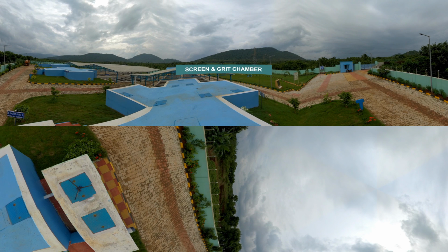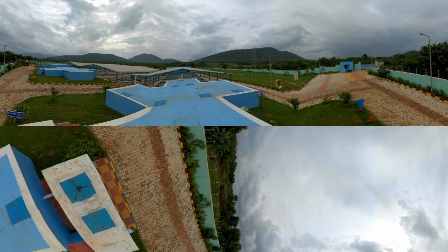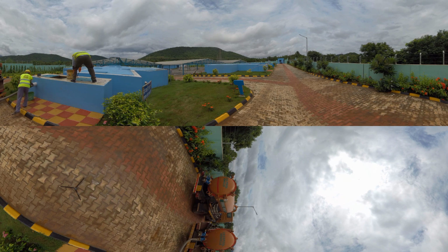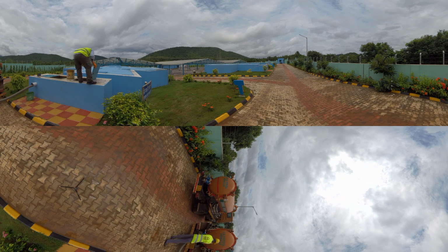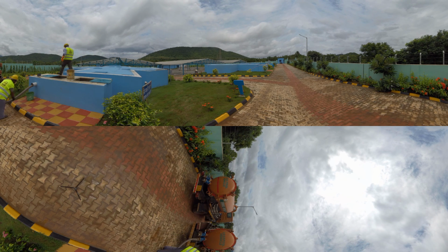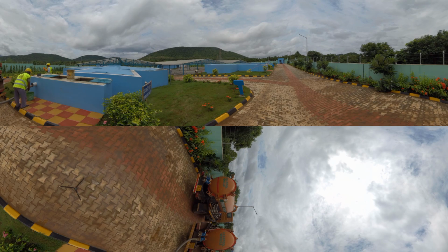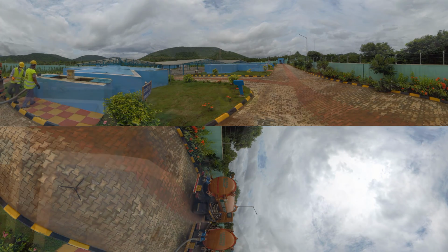Screen and grit chamber. In our treatment process, screening is the first step in which large solid objects such as sanitary pads, pieces of clothing, paper napkins, razors, cigarette butts, match boxes, bottles and other municipal waste are filtered out from the sludge. These objects are trapped in the screen and have to be removed from the screen chamber after each load is disposed of into the FSTP. The settled silt should be cleaned at least once a week.